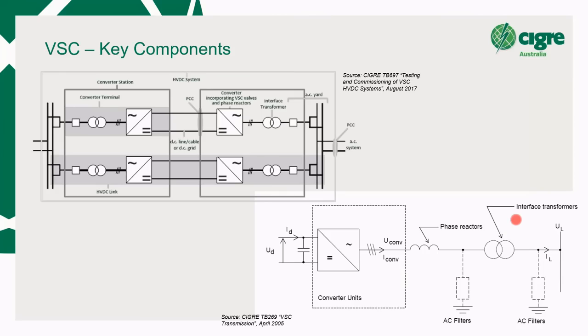Some people in CIGRE call them interface transformers. It's a term that's popped up. But anyway, they're transformers. They go through phase reactors into the converter units. The AC filters may or may not be required depending on which topology you use, because different VSC topologies have different numbers and degrees of magnitude of harmonics, okay? So you may or may not need AC filters depending on what topology you use.